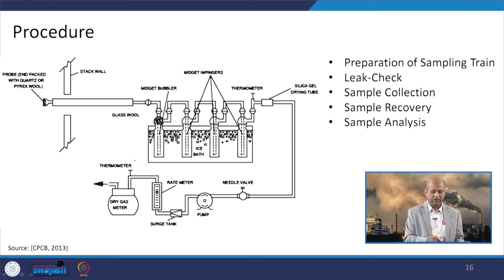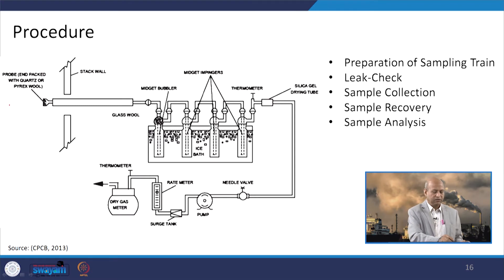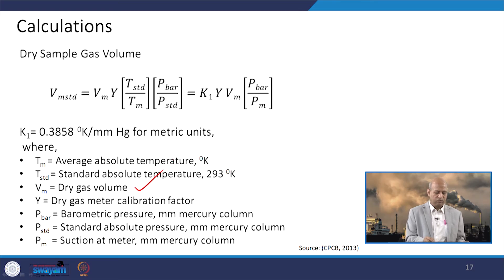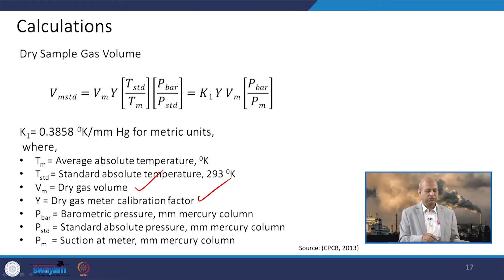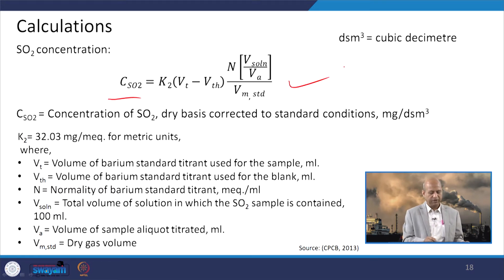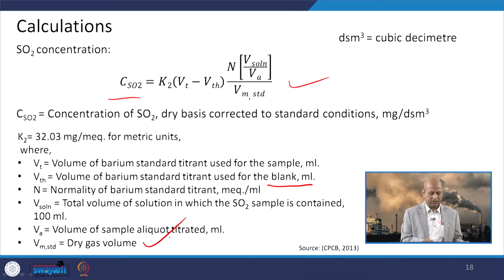The procedure is shown in a schematic diagram: the sample is collected, recovered, and then analyzed in the laboratory. The sample goes through impingers where it is absorbed, and then taken to the lab. Calculations for SO2 are similar to those for particulate matter — temperature, volume, calibration factor, and pressure-related factors are used for gas volume calculation. The SO2 concentration is calculated using the volume of barium standard titrant used for the sample versus the blank, along with the dry volume and volume of the sample.